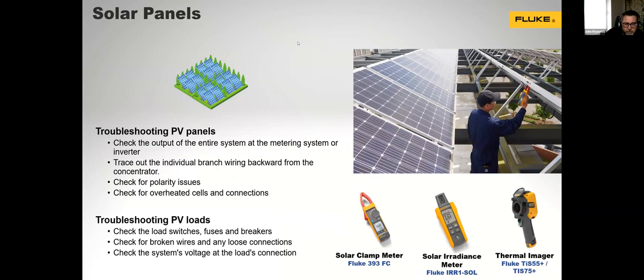For solar panels, when we troubleshoot these panels, we'll be checking the output of the entire system at the metering system or the inverter, tracing out the individual branch wiring backward from the concentrator, checking for polarity issues, and checking for overheated cells and connections. For troubleshooting the PV loads, we need to check the load switches, fuses, and breakers, check for broken wires and loose connections, and check the system's voltage and load connection. Now, we've got 3 products that can do this, but you can use others. We've got the clamp meter, the 393, we've got the solar irradiance meter, as we've mentioned, and again, a thermal imager starting off at the TIS 55 plus.